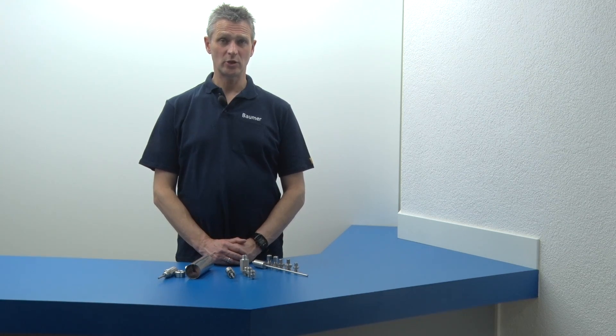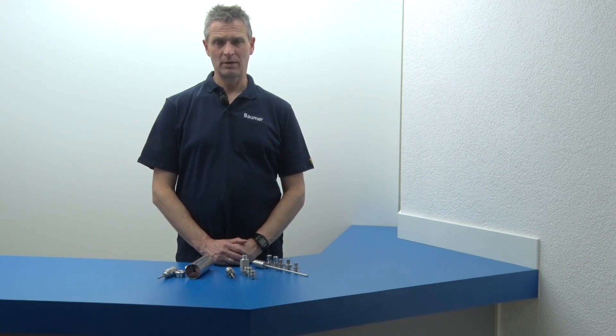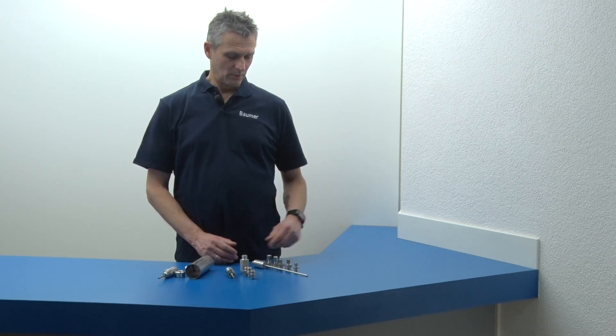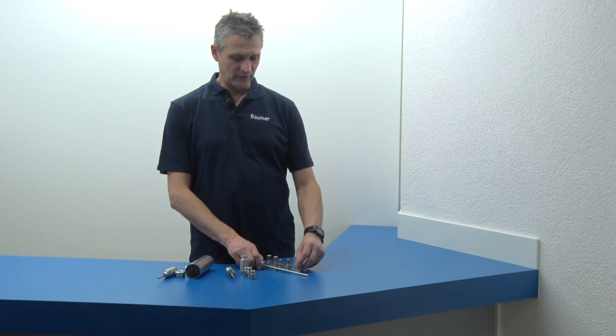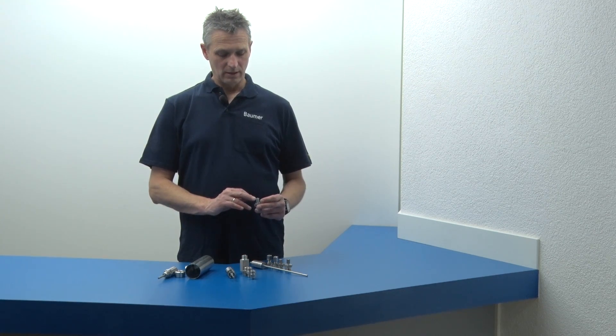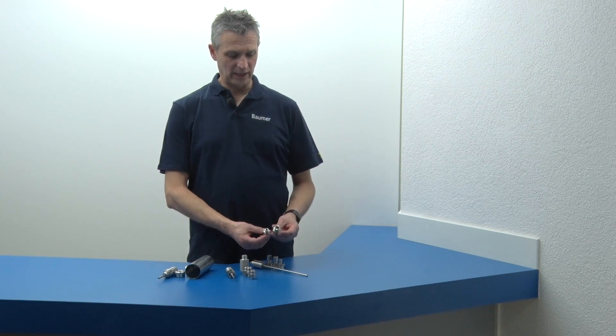Our adapters can be directly screwed or welded onto pipes or tanks, as every Baumer process sensor can be. Using different sealing with the sliding variant makes the connection endure different pressures. This is the 6-bar variant with screw adapters sized 1 1⁄4-inch.